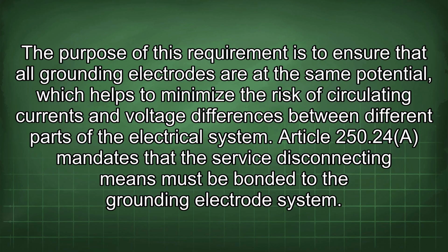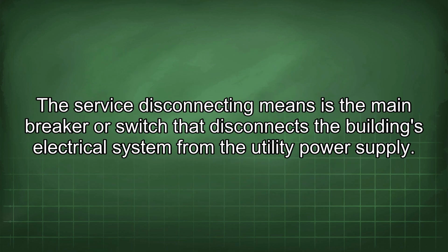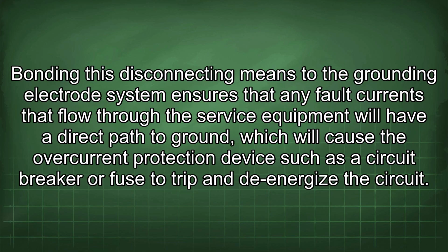Article 250.24 mandates that the service disconnecting means must be bonded to the grounding electrode system. The service disconnecting means is the main breaker or switch that disconnects the building's electrical system from the utility power supply. Bonding this disconnecting means to the grounding electrode system ensures that any fault currents that flow through the service equipment will have a direct path to ground, which will cause the overcurrent protection device, such as a circuit breaker or fuse, to trip and de-energize the circuit.